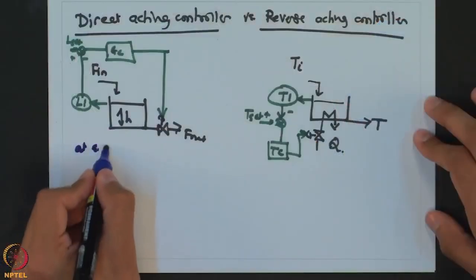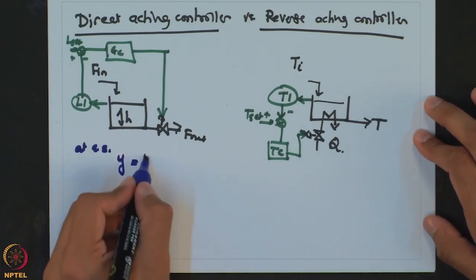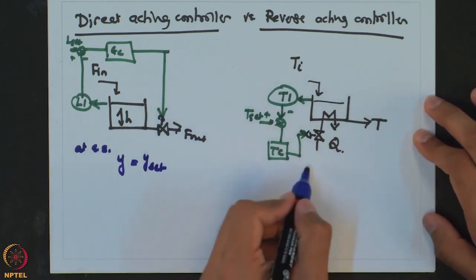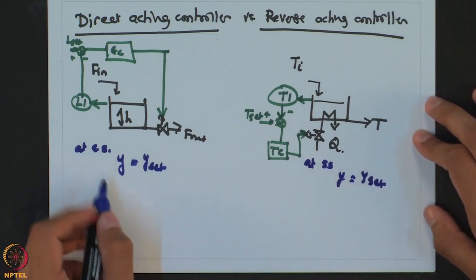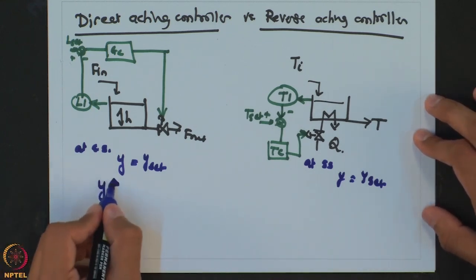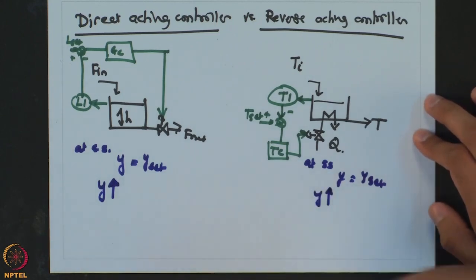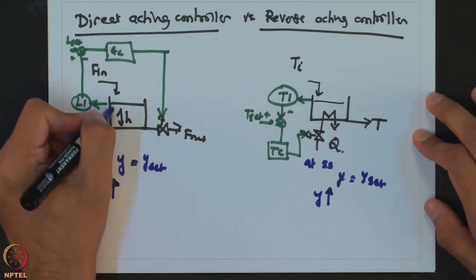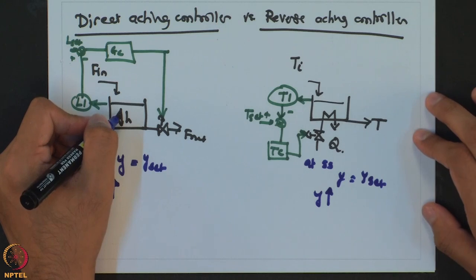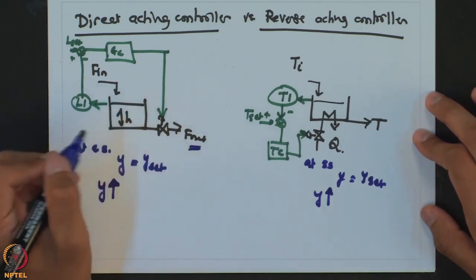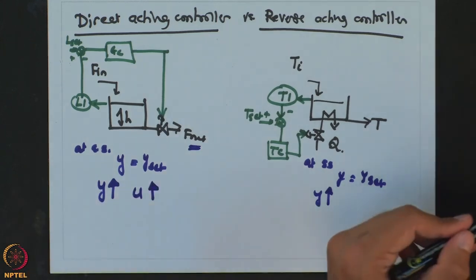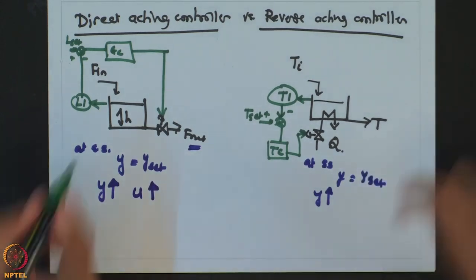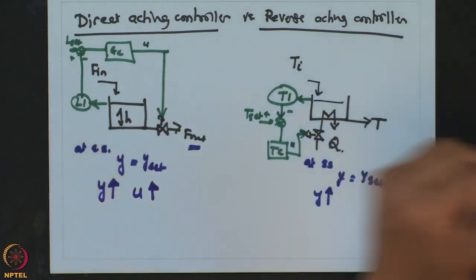Welcome back. In both cases, at steady state the output equals the set value. Let us say at some finite time, because of a disturbance, Y increases beyond the set point. In the level control case, as Y increases — meaning the height inside the tank increases — the control action needed is that the controller output should also increase. So if I represent U as the controller output, it has to increase when height increases, which ultimately results in an increase in F out.